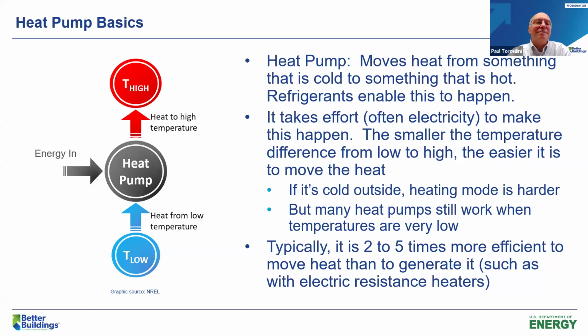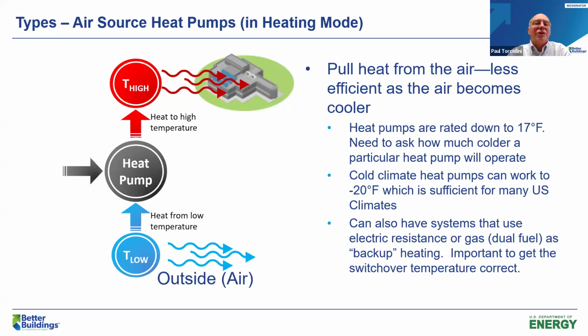So go to the next slide. Using that same schematic and showing heating mode, we're pulling heat from the outside air, which actually makes the outside air a little bit cooler. We're putting effort into the heat pump, again usually electricity, and we're producing heat at a relatively high temperature, at least high enough that we can use it to heat the building. Many heat pumps are rated down to 17 degrees Fahrenheit, and there are definitely heat pumps out there that will operate much colder, down to 20 below or even lower than that today.